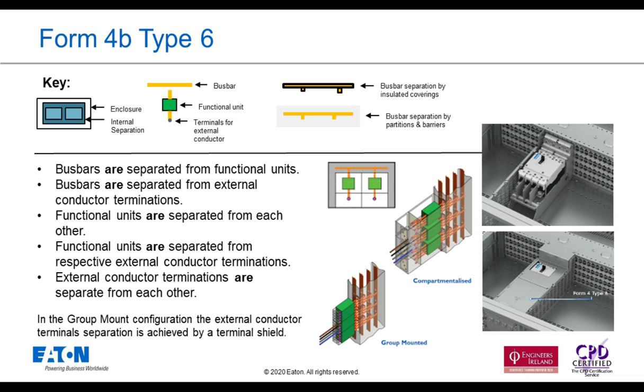Form 4b Type 6, I would say this is now probably, along with Form 4 Type 2, Form 4 Type 6, definitely the market trend these days. So here you've got your main busbar shrouded using a partition or a barrier. Your functional units are sitting in their own compartment, although it can be done as a group mounted as well, but it's not very common. And then you've got your external cable terminals in their own compartment as well.